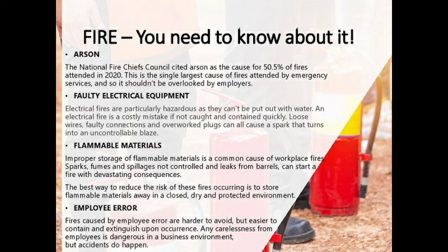Faulty electrical equipment is particularly hazardous as electrical fires cannot be tackled with water. Many workplaces only have water extinguishers, which cannot be used on electrical fires — consider CO2 for office, server, or electrically-dense areas. Electrical fires are also costly because they can spread through wiring to different parts of the building. Loose wires, faulty connections, and overloaded plugs and extension leads can cause sparks leading to uncontrollable blazes. Ensure extension leads are appropriate for the equipment connected to them.